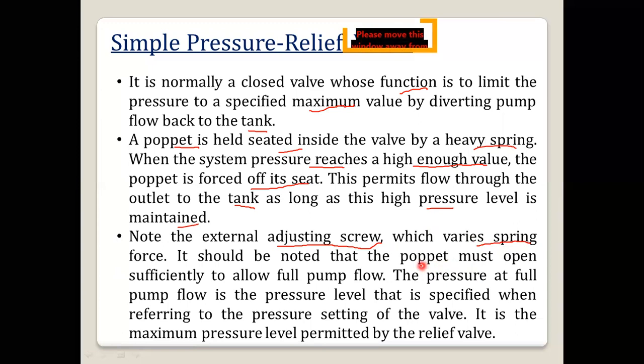Okay, so it should be noted that the poppet must open sufficiently to allow full pump flow, and the pressure at the full pump flow is the pressure level that is specified when referring to the pressure setting of the valve. Okay, so the full flow pressure is the maximum pressure level permitted by the relief valve.